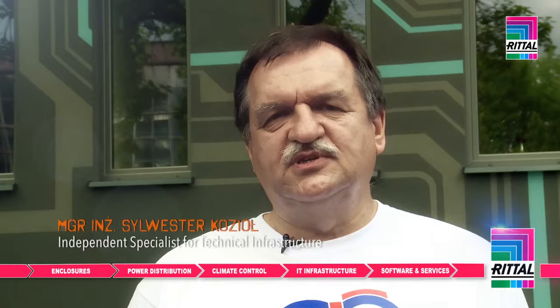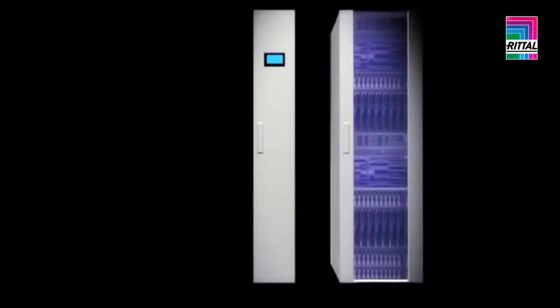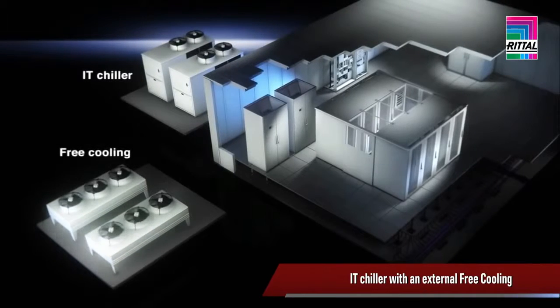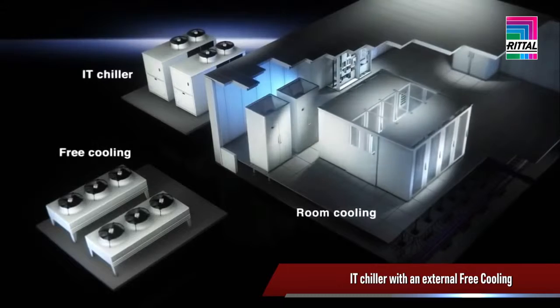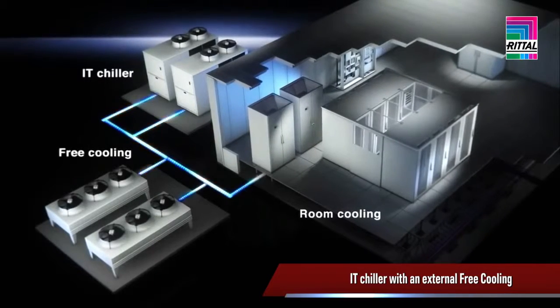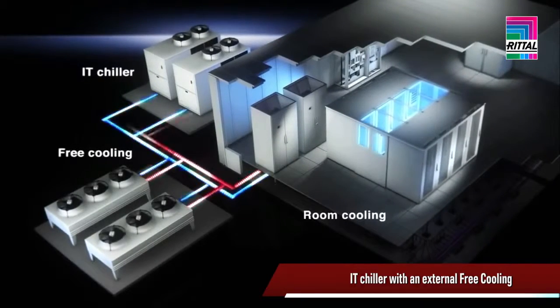On the roof there are 2 Rittal chiller units with cooling capacity of 406 kilowatts each. Those are cutting-edge units that switch to free cooling mode automatically whenever ambient conditions permit, which is when the temperature is sufficiently low. Free cooling doesn't require using the compressors.